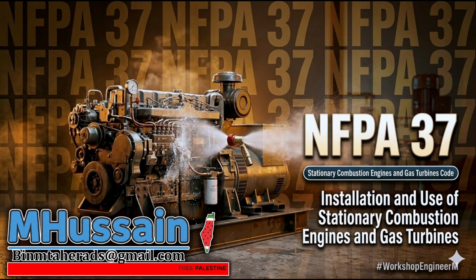Okay, so we've given the beast space, we've given it air, we've routed the exhaust, now we have to feed it. The most volatile part of the system. Right. Pumping highly flammable liquids or gases directly into a vibrating hot machine. This is where NFPA 37 intersects with NFPA 30, right? The liquids code. Yes, and the regulations are incredibly strict, starting with material bans.